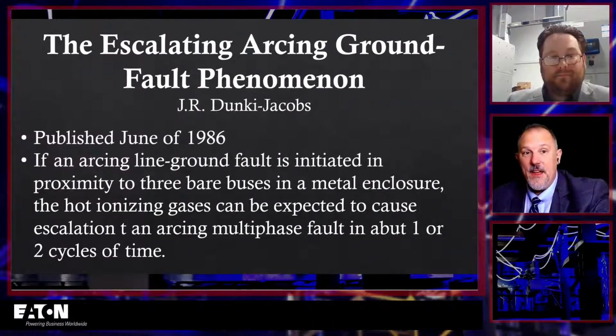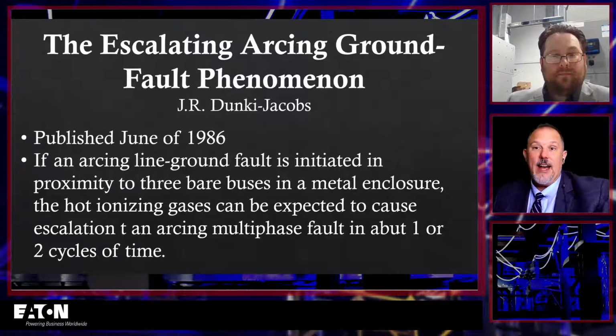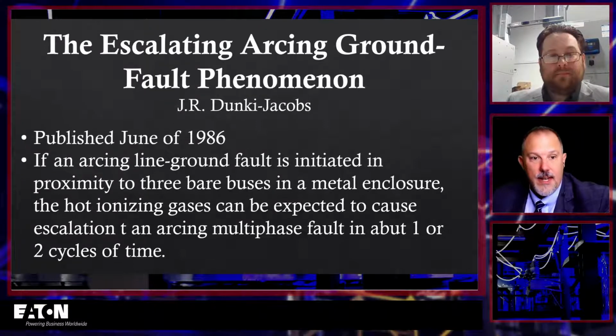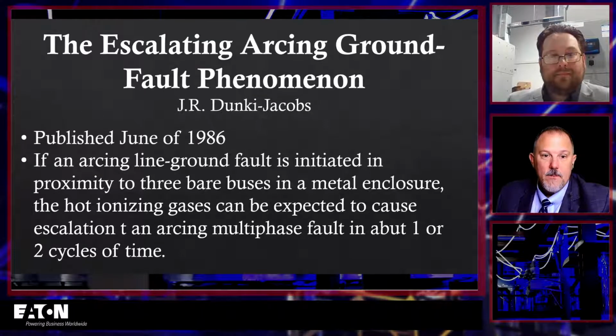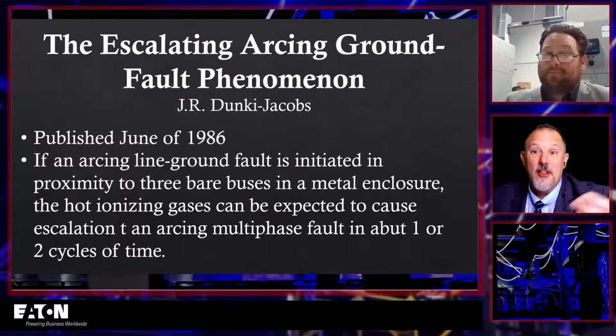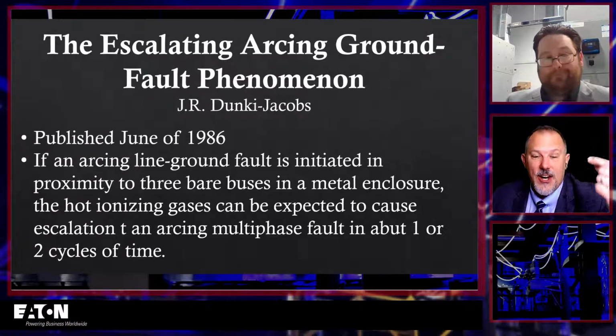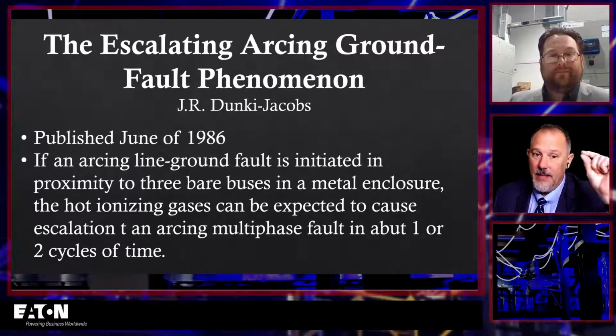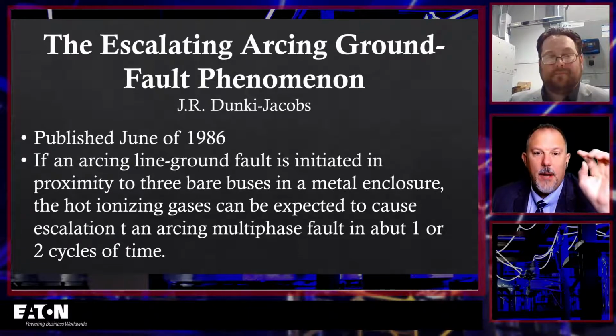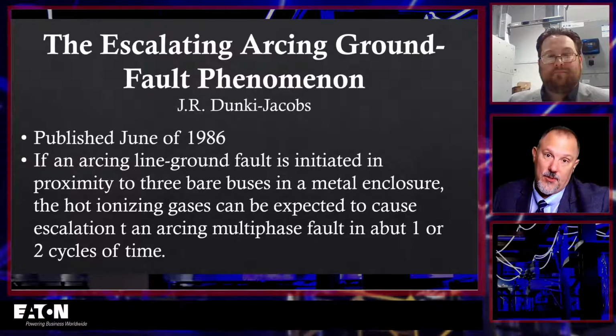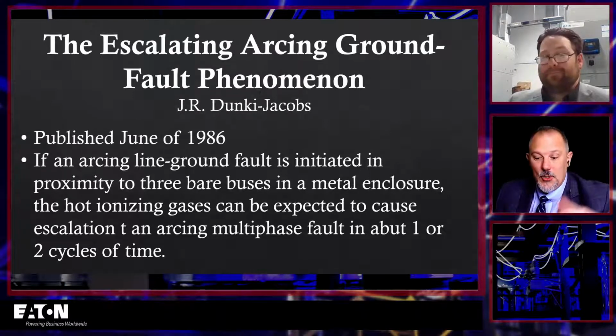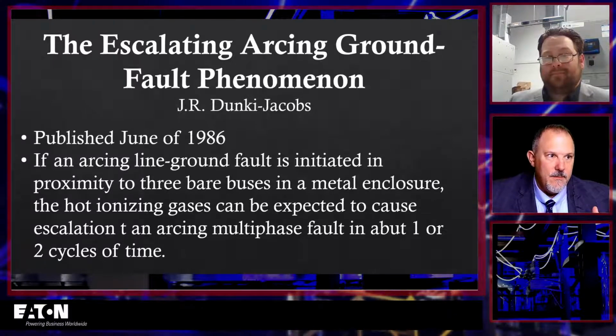And then Dunki-Jacobs in 1986. So after GFPE went in the code in '71, Mr. Jacobs says, hey, look, in June of 1986, what he showed was that if an arcing line to ground fault is initiated in proximity to 3 bare buses, which, what do you have? When you've got a 4,000 amp piece of equipment, you got a lot of bare bus in there. The hot ionizing gases will cause escalation to an arcing multi-phase fault in about 1 or 2 cycles of time.